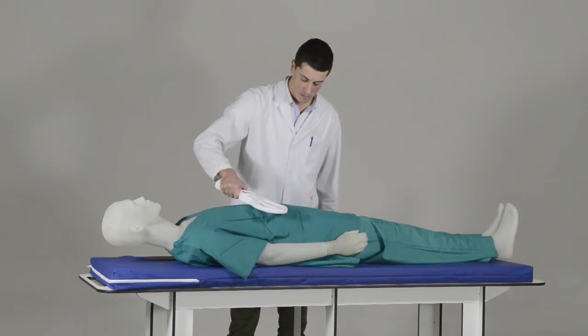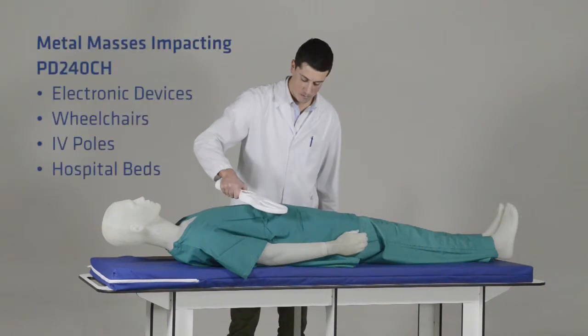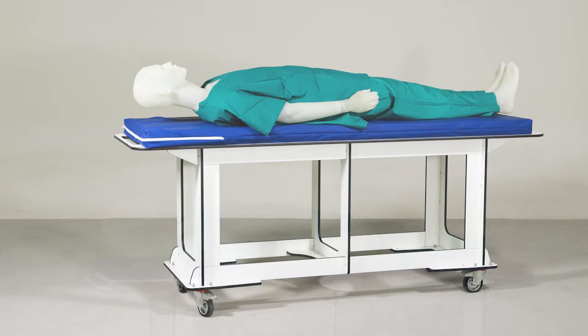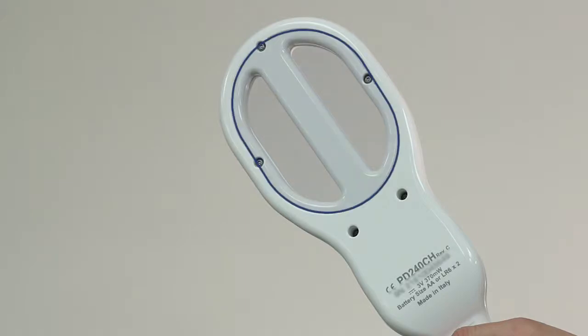This includes objects such as other electronic devices, wheelchairs, IV poles, hospital beds, etc. It also includes things that may not be as obvious, such as the floor, walls, doors, or furniture. It is recommended to maintain a minimum distance of 16 inches from the floor and 20 inches from all other objects during the screening process. However, it may need to be further depending upon the size of the mass. The sensing area of the device is indicated here.